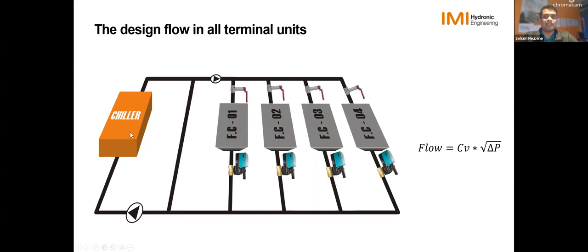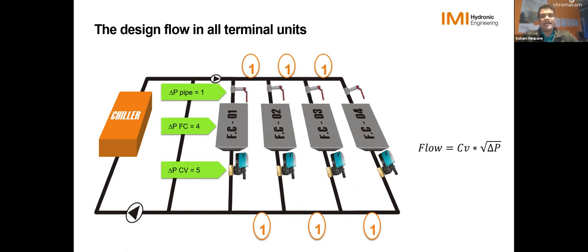With a system, we've got a chiller, a primary pump, a secondary pump, and we've got 4 circuits here with fan coils. And we've got bypass and all built in as well. So, it's a well-designed system. And we're gonna consider some pressure drops here. So let's say we've got 1 feet of pressure drop in the piping in each of these circuits. We've got 4 feet of pressure drop on the fan coil and 5 feet of pressure drop on the control valve. And we've got 1 feet of pressure drop basically on your supply and return distribution pipes here. Okay, so remember earlier we talked about how with manual balancing, we're adding the right amount of resistance so that we have the equal differential pressure throughout the building, right? And that's exactly what we're gonna see, how we do that.